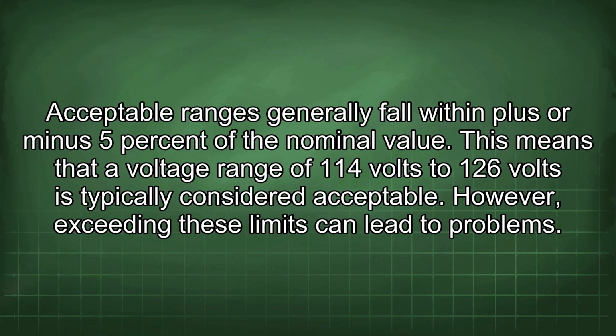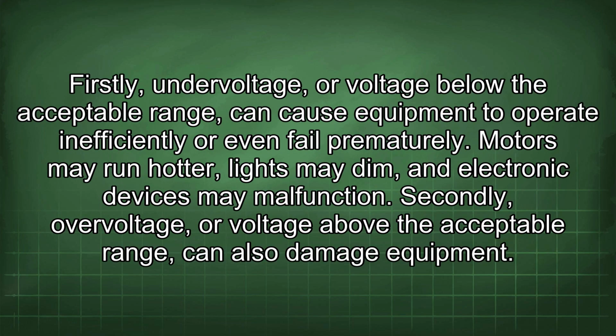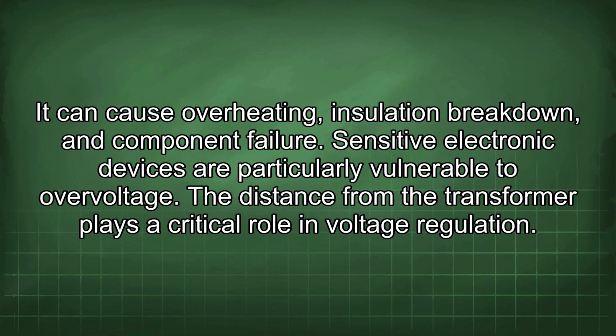However, exceeding these limits can lead to problems. Firstly, undervoltage, or voltage below the acceptable range, can cause equipment to operate inefficiently or even fail prematurely. Motors may run hotter, lights may dim, and electronic devices may malfunction. Secondly, overvoltage, or voltage above the acceptable range, can also damage equipment. It can cause overheating, insulation breakdown, and component failure. Sensitive electronic devices are particularly vulnerable to overvoltage.